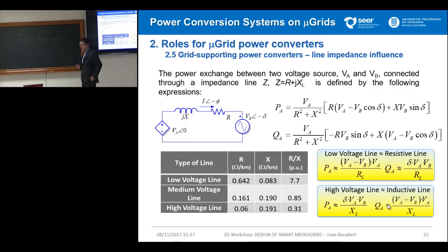As we saw, there is a large dependence between the droop curves and the line impedance, depending on whether we are in a resistive or an inductive line. So it is very important to know exactly the grid impedance, and this is a problem because the grid impedance changes.